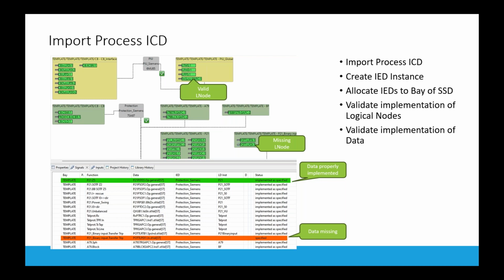Then we can automatically implement the source ref element, which was the specification inputs that we created in the substation specification part, the previous part. The system also gives you information if, in this case it's no longer the case with the latest file, but in one file we had one signal which was not mapped in the process ICD, and the system tells you this signal is, for example, missing in the process ICD. So you have some feedback.